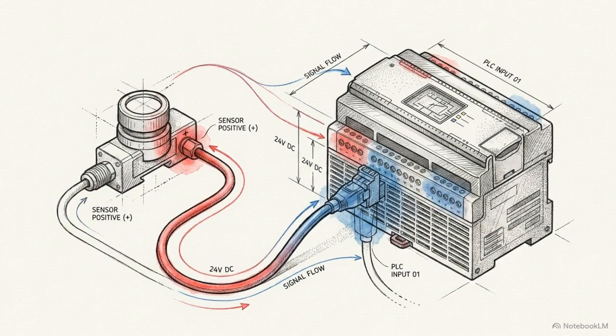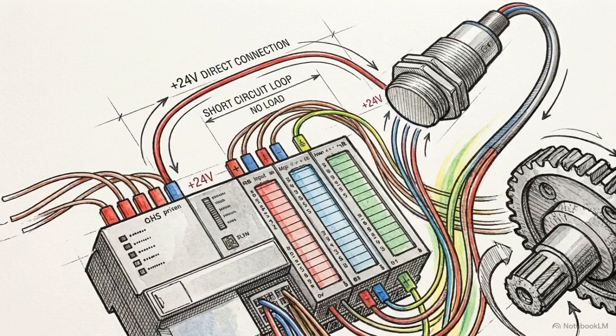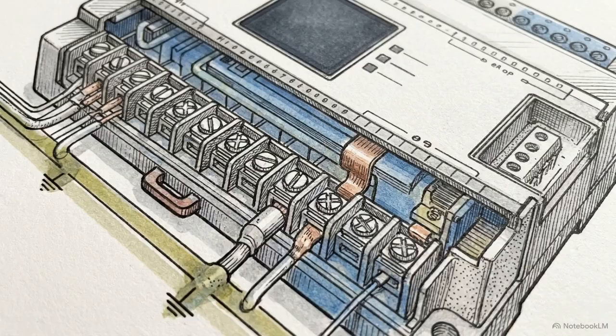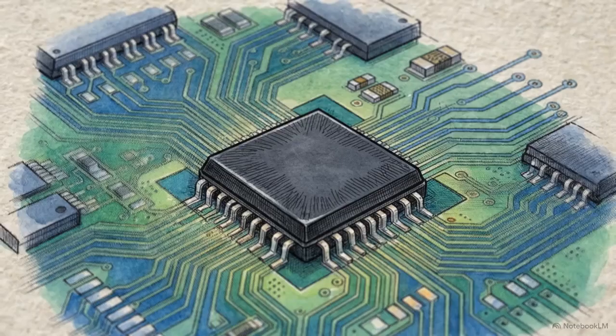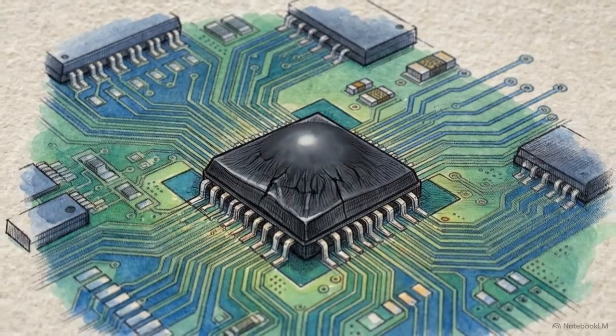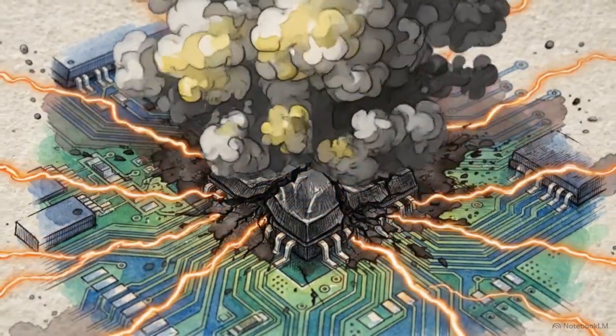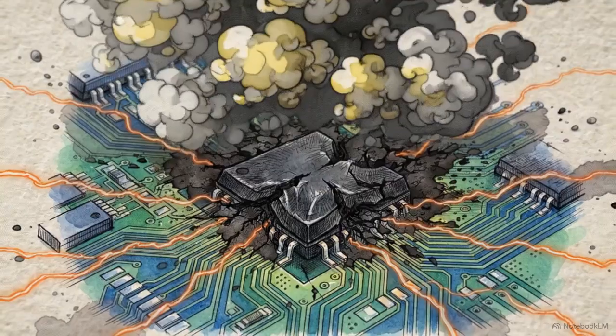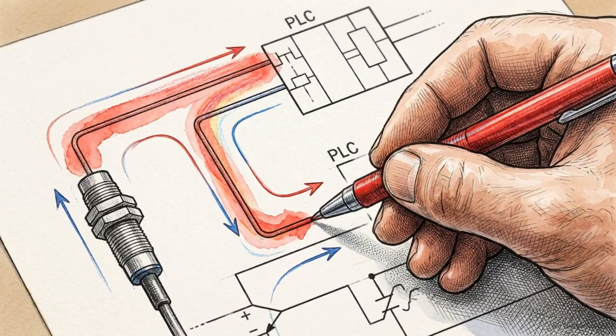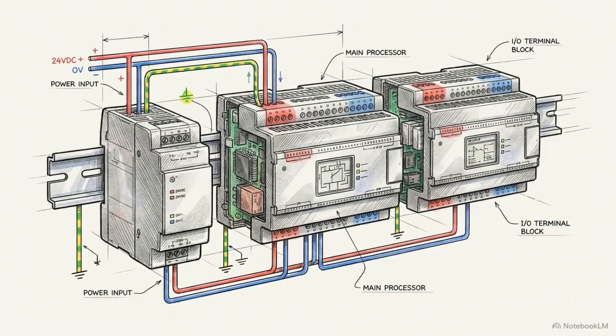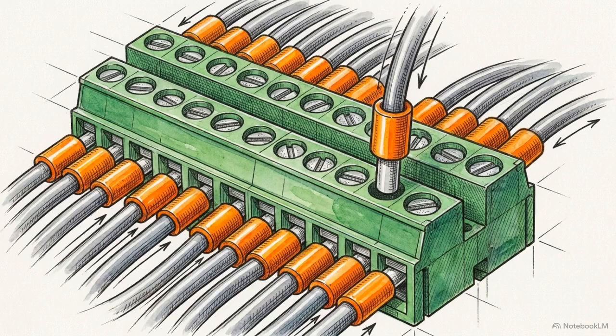Wiring a PNP sourcing sensor to a PLC input that is also configured to source current creates a direct conflict. Two positive potentials face each other, resulting in dead inputs that refuse to trigger. If the error bridges a ground path, you create a direct short circuit that will instantly melt the internal optocouplers of the PLC hardware. Mastering the direction of current flow renders hardware differences irrelevant. Whether you are wiring a Siemens, Delta, or Mitsubishi controller, the laws of circuitry dictate exactly how the devices must connect.